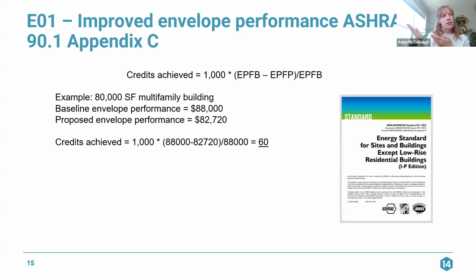I popped in a picture of ASHRAE 90.1 here. The entire modeling protocol is fairly light, but you do have to provide a report that discusses all of your modeling inputs, provides a zone diagram, items like that. So this isn't just something where you can input the dollar amounts. You do have to actually provide a full report for the reviewer at the time of permit submittal.